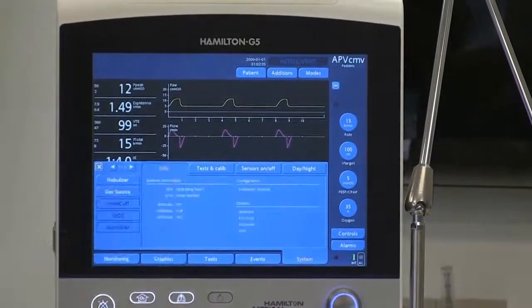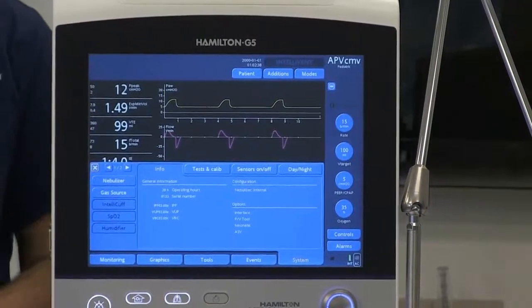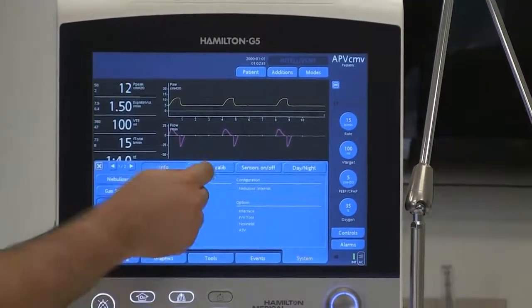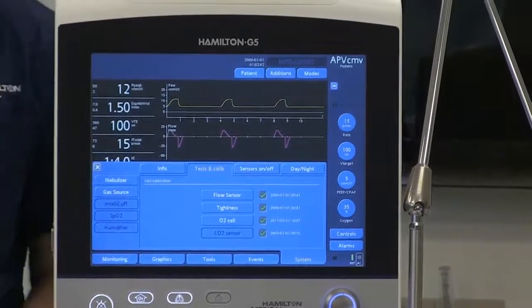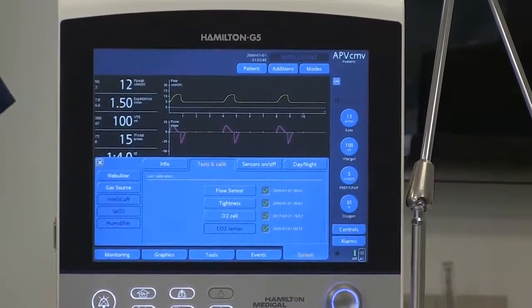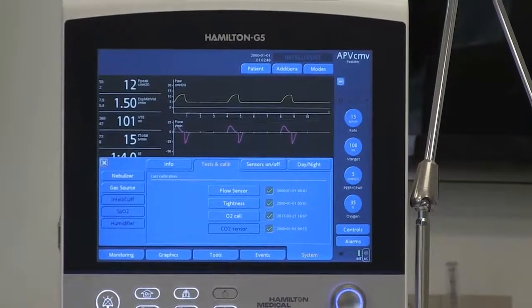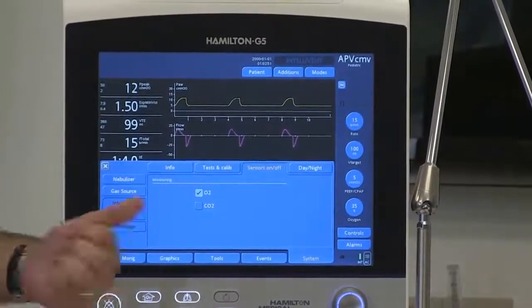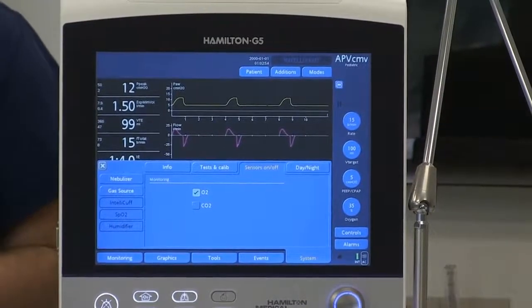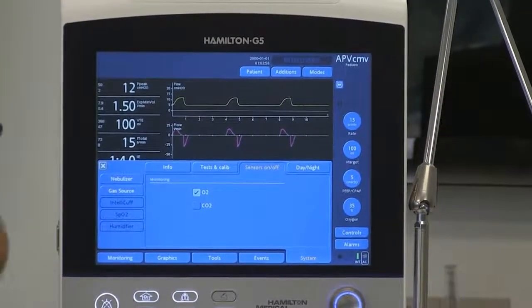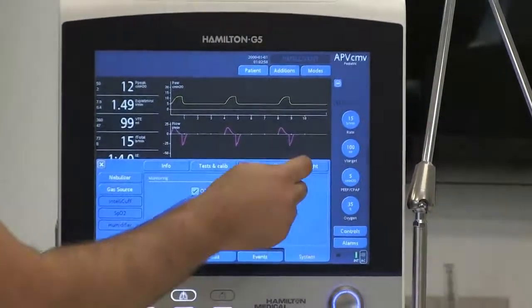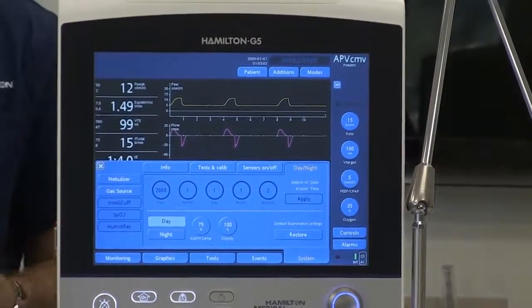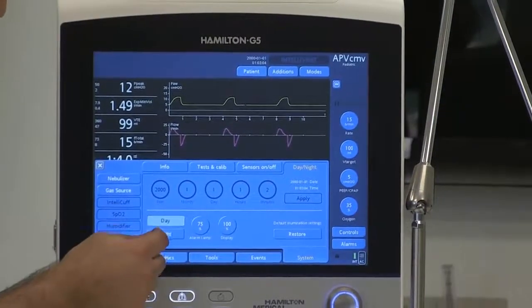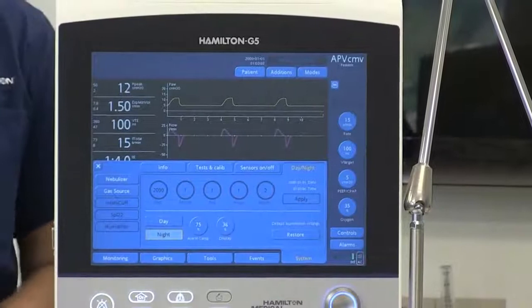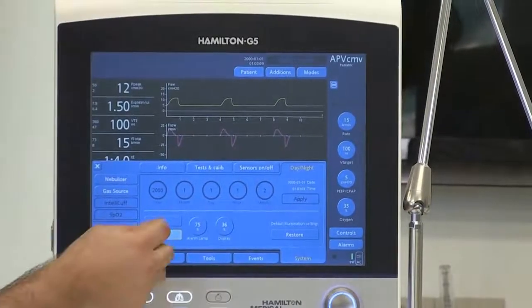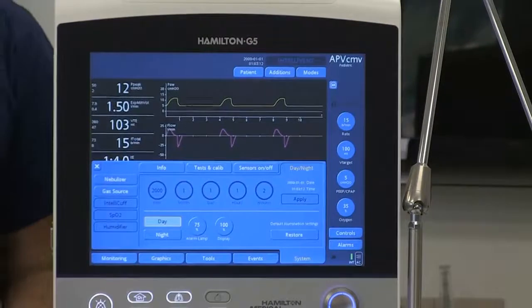Going up here, info will give you the software version of your ventilator. Test and calibration will allow you to see all of the calibrations and when they were last performed and completed. Sensors on/off. This is where you would toggle on either your carbon dioxide sensor or your O2 sensor. Day-night mode is where you can configure the brightness of your screen. By simply pressing night mode, the screen dims, offering less patient stimulation at night. And by clicking day, the screen brightens.